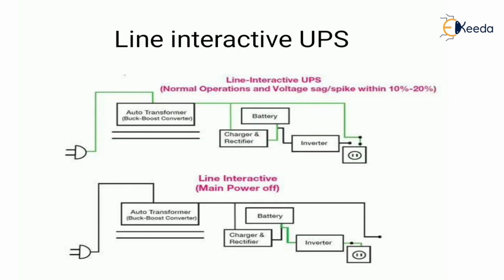Next is line interactive UPS. A line interactive UPS contains an auto transformer, or you can say a buck boost converter, that boosts the main power supply when it falls. So it can regulate the power to an acceptable level without the use of battery during the brownout or the surge in the supply voltage. Similar to an offline UPS, there is a short period when the line interactive UPS switches to the battery mode during a blackout.